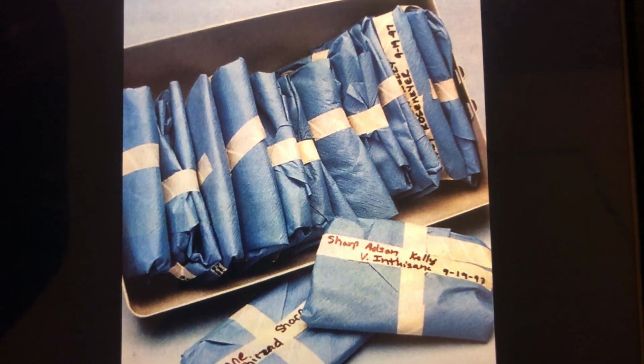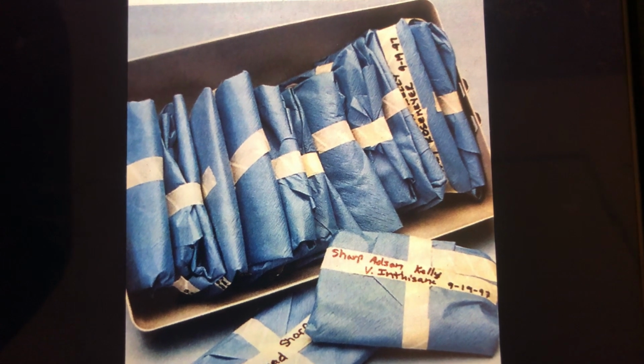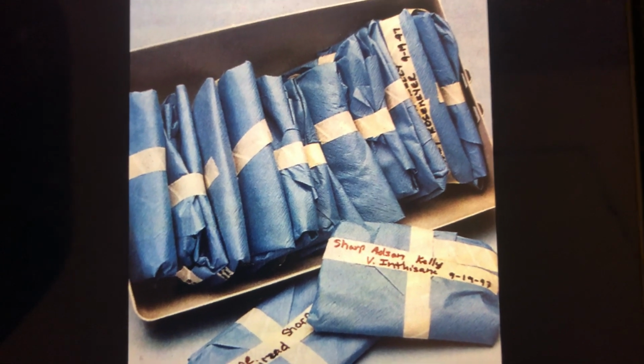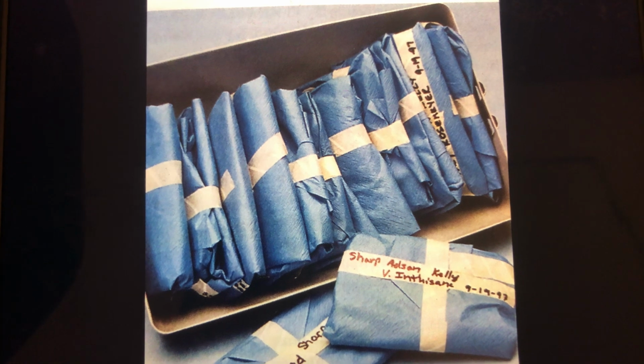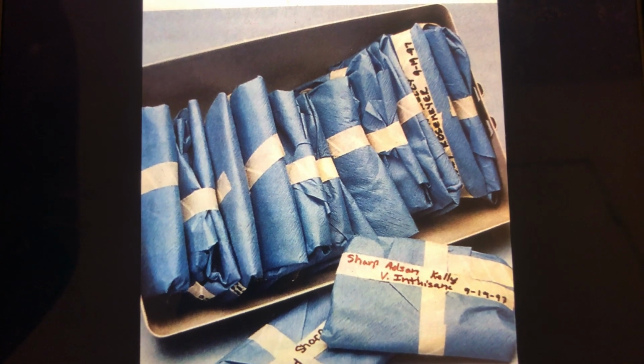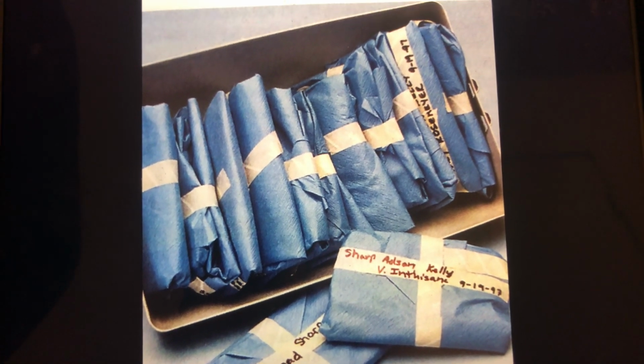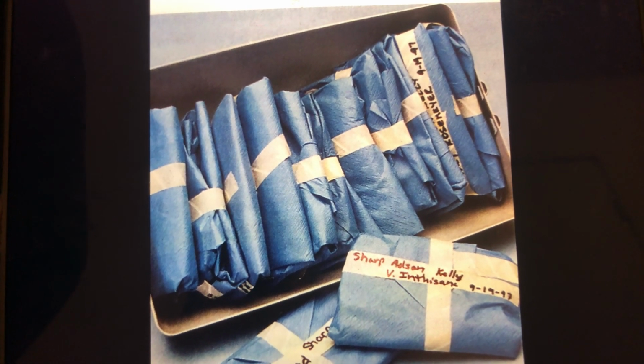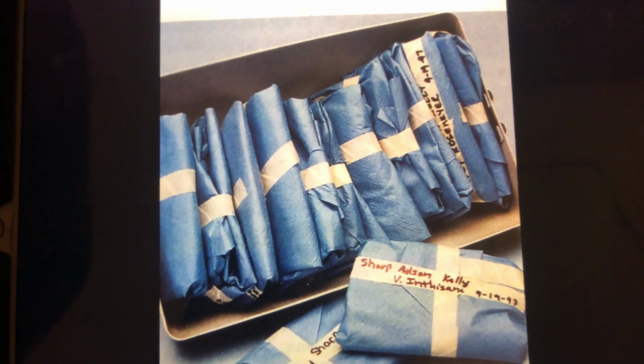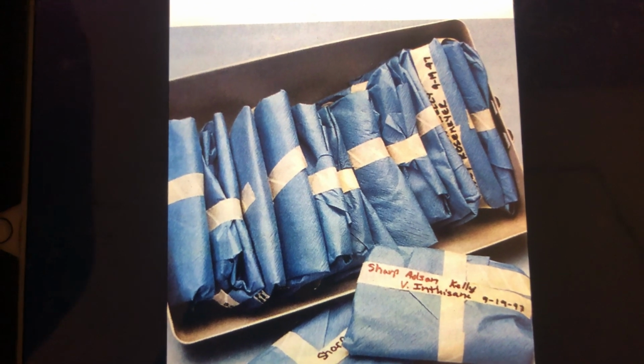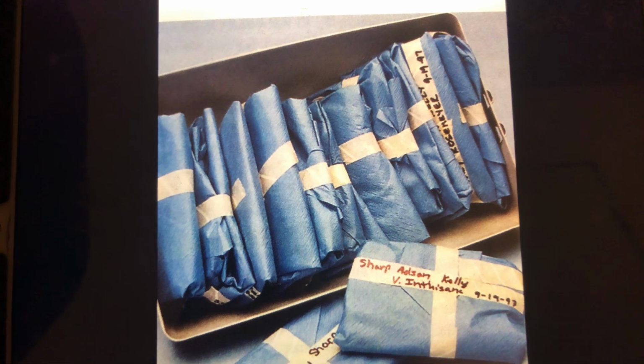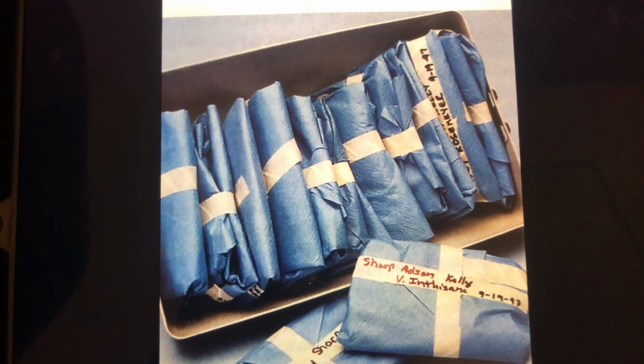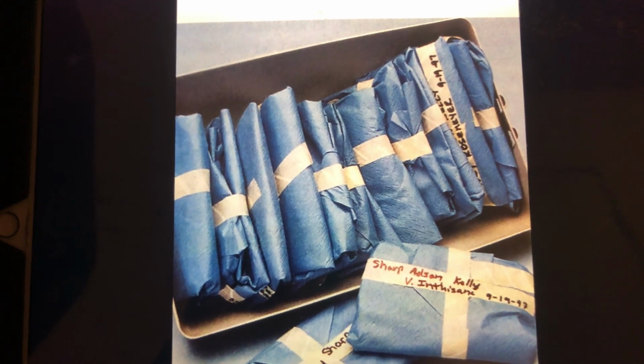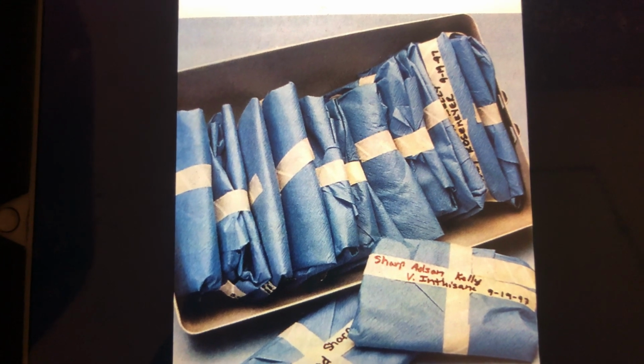The equipment you will need is autoclave wrapped items ready to be sterilized and heat resistant gloves. You will have to check the water level in the reservoir and add distilled water as necessary. You will have to turn the control to allow water to flow into the chamber. The water flows until you turn the control to its next position. Do not let the water overflow. Load the chamber with wrapped items, spacing them for maximum circulation and penetration.